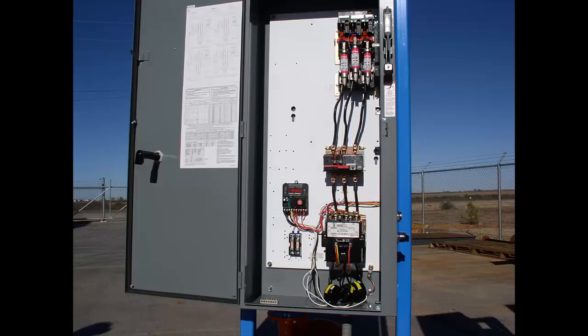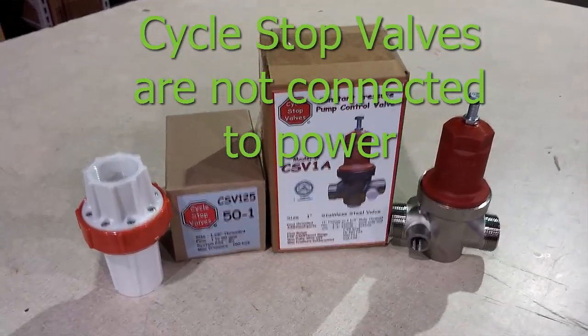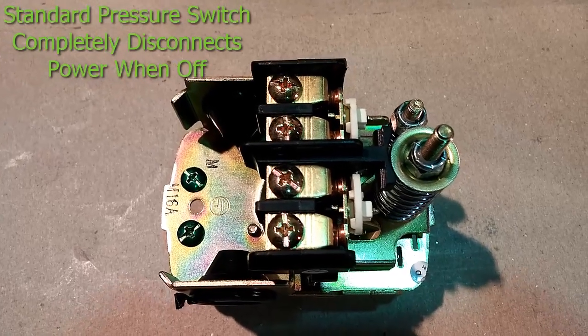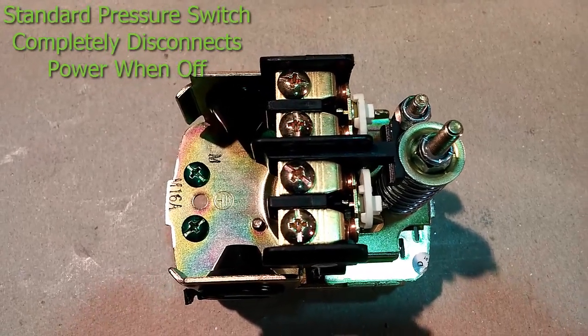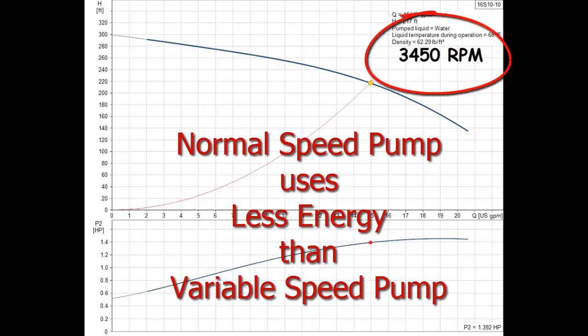Running on across the line, true sinusoidal power, direct from the grid or generator, a normal full speed pump is more efficient. Because the CSV does not use electricity and the standard pressure switch completely disconnects power from the pump, there is zero power used when the pump is off. So now that you know the power consumption for a normal full speed pump can be less than a variable speed pump, let's discuss how a cycle stop valve or CSV can deliver the same constant pressure performance as a VFD.